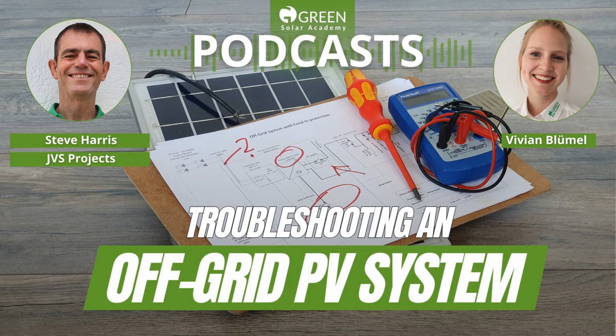And then I'll measure the voltage coming in from the PV array. So we'll check and see if that's systematic. If there's more than one string, we'll check that the strings are all matching each other. If it's an east-west scenario, we should expect a difference. Let's see what the difference looks like. We'll have a look at the fundamental integrity of the installation. We'll test that every cable is tight. We'll check that there's no sign of overheating. We'll see that the fuses are correct.